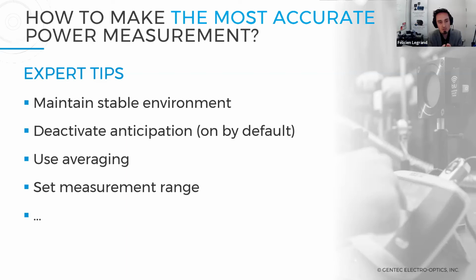Deactivate anticipation. Anticipation is a feature that we provide with our detectors. It's a software-based feature. Basically, we look at the increase in power using a thermopile detector, a thermal detector. The reading is not stabilized instantaneously. It takes some time for the energy to be absorbed by the absorber and transferred to the thermocouples, or the water if it's a calorimeter. So you have a ramping up in power, and the software looks at this increase to derive a stabilized output measurement. Knowing the physics of the thermopile, it knows that if it sees this kind of increase in temperature, the power will stabilize at this level.